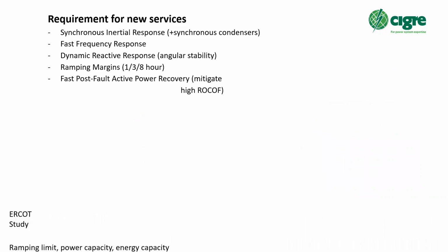So now you need new services: synchronous inertial response, faster units, and synchronous condensers. You need fast frequency response at the primary control level, dynamic reactive response for angular stability, ramping margins now given in 1, 3, and 8 hour intervals, and fast post-fault active power recovery to mitigate high rate of change of frequency.